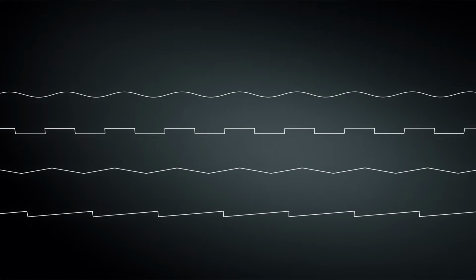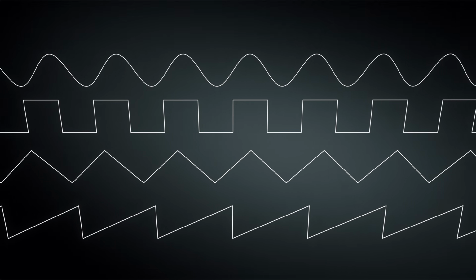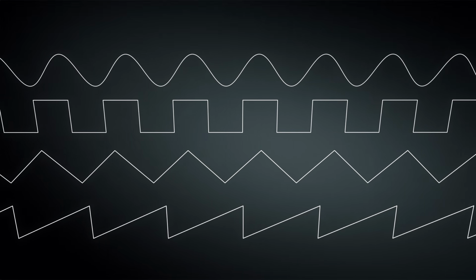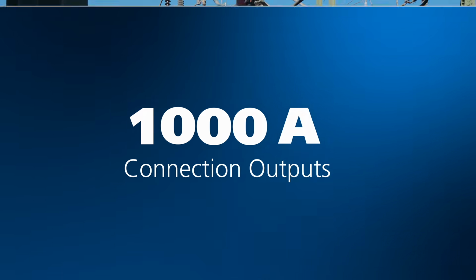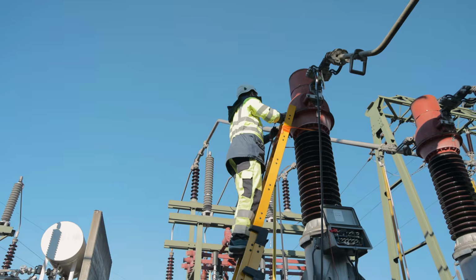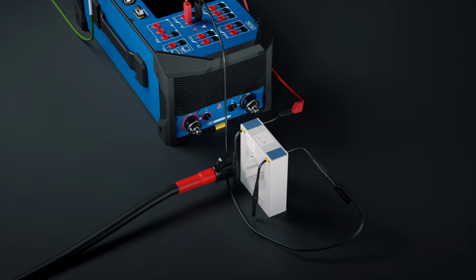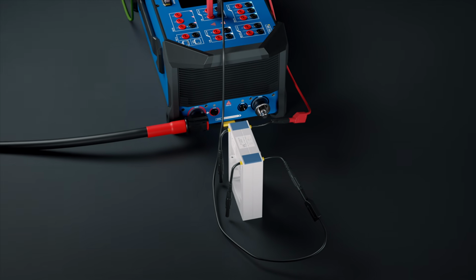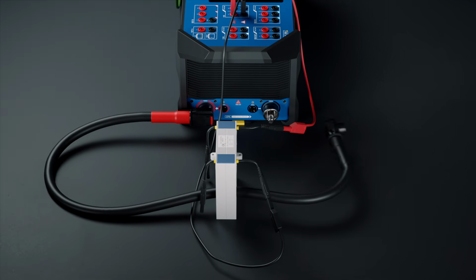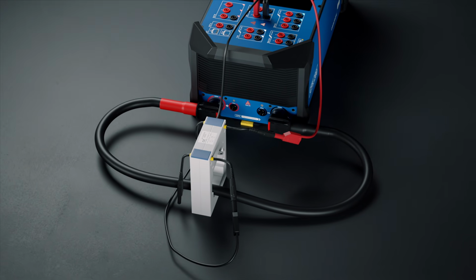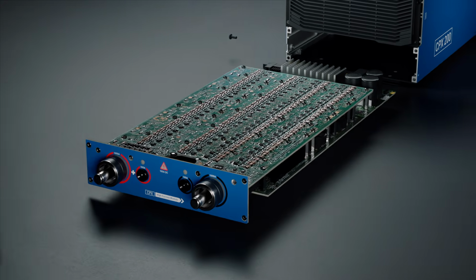Since we use power electronics instead of conventional transformers, the CPX 200 not only generates sinusoidal signals, but also generates square wave signals, sawtooth signals, or any other periodically recurring signal shapes. Furthermore, these power electronics enable you to generate pure DC that has no superimposed hum, making the CPX perfect for resistance tests on inductances. The 1000 amp connection outputs are a unique highlight. Cables and clamps are designed to offer the most suitable wiring solution for each specific application. A cable can be looped without using a clamp for ring core current transformers. By contrast, when working with switchgears, the cable can be secured to the bolt to ensure an optimized connection, even in confined spaces. So that's the high current module.